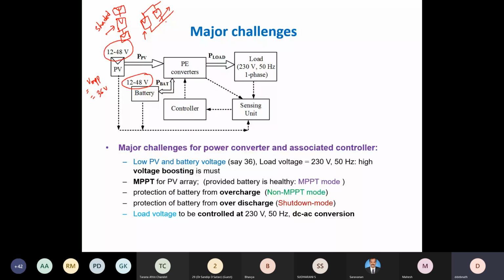Same thing applies for battery. The thumb rule for battery is that if your power rating is less than 500 VA, you go with a 12 volt battery. For 500 to 1000, you go with 24. Then you go with 48, maybe up to 5 kVA. And after that, you go with 96. This is typically the rough figure.